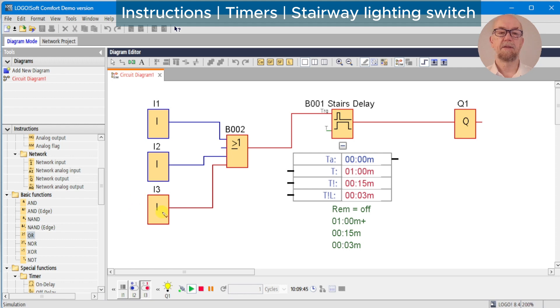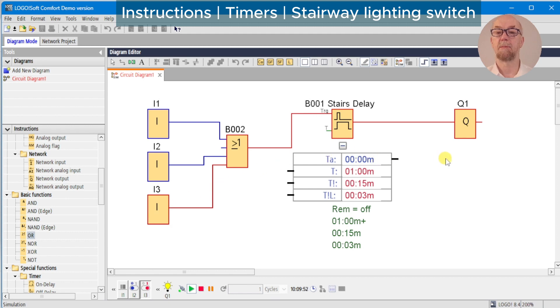In this case I've used a toggle switch for input three, and you can see that that's a bad choice — it has held the timer low so the timer will never expire. That may be useful in certain locations but not for a typical stairwell application.